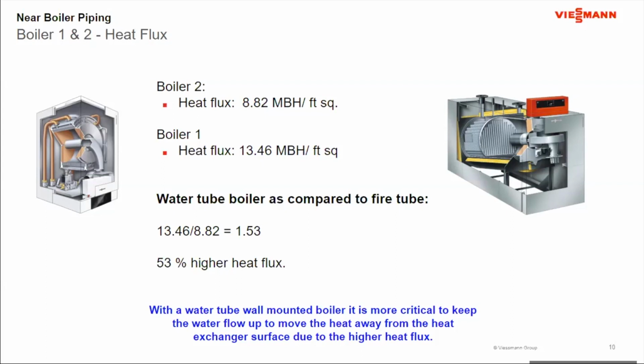So when I look at the water tube wall-hung boiler, because of this higher heat flux, it's much more critical to keep water flow across that heat exchanger. Remember, this is only a 4-gallon boiler. That water flow across the heat exchanger pulls the heat off of that heat exchanger face to allow the boiler to operate properly. So again, this becomes another point of discussion when we talk about whether I'm going variable primary or primary secondary.